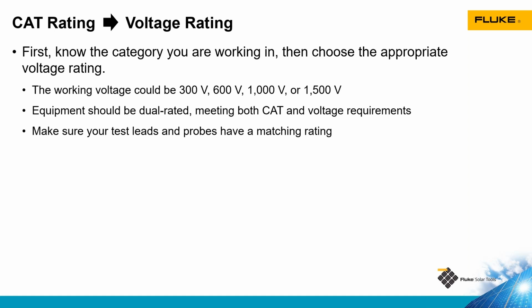Our test leads must be rated equal to our test meter. What can commonly happen is you have a meter like the 393 clamp meter, which is 1,500 volt rated Category 3. It has 1,500 volt rated Category 3 test leads, but if those leads should be damaged or misplaced, it would be common for someone to just grab whatever set of test leads they have laying around. And there's a pretty good chance that those are not going to be rated at the same level as those 1,500 volt test leads. So make sure that the rating of the leads matches the rating of the test equipment.